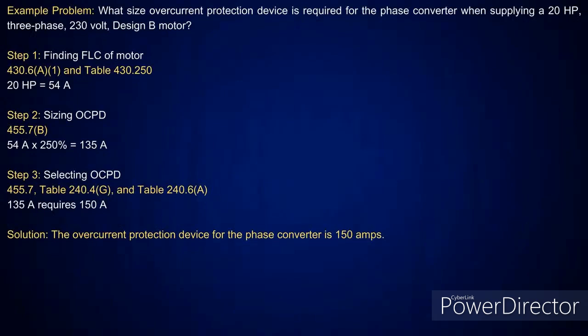Okay. Now, the next thing we're going to do to get you ready for next week in the homework, the first one we're going to do here is we're going to be looking at sizing the overcurrent protection device where I have a phase converter. So in this case, I've got a 20 horsepower, 3-phase, 230 volt design B motor. Now, like I said, when you're sizing the overcurrent device, 430.6A1 will tell you to go look at the tables. In this case, since it's a 3-phase, we're looking at table 430.250. And if I pick up my 230 volts and I come down, pick up 20 horsepower, it's going to tell you it's good for 54 amps.